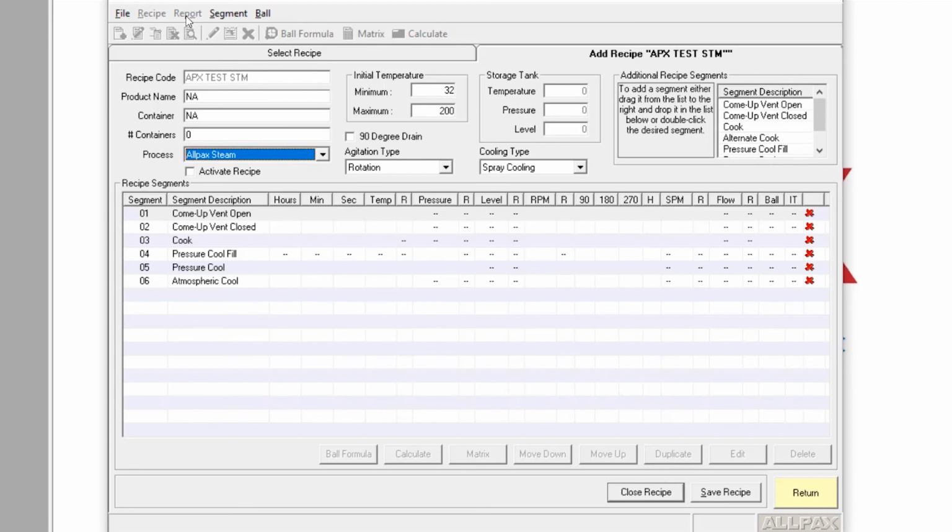This is where you decide what you'll accept. If it's important that the product goes into the machine at 140 degrees, plus or minus 5 degrees, then this is where you would set that range. If the product doesn't fit in that range when you put your IT in, when you start the process, the machine won't start. The machine won't start running the recipe.